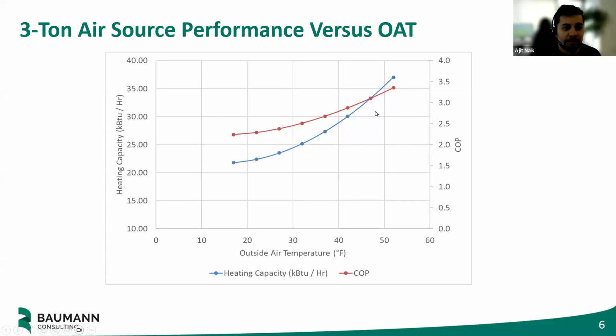So these air source heat pumps, which is the most common heat pump that you'll see, or when you go to Costco or Home Depot and the person at the exit tries to get you to buy a heat pump unit, this is usually what you're seeing. The technology has really improved a lot, right? Over the years, the low end temperature used to be 30, 40 degrees. Now you can get these units working down to -5, -10, and even colder than that. But ultimately, it's something to keep in mind, right? That when you're using air source heat pumps, the efficiency and the capacity drop.